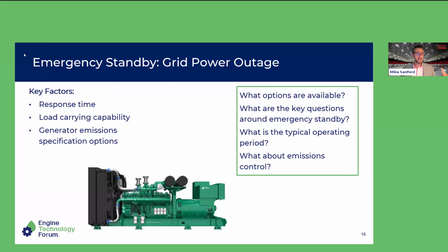That transfer could result from a total failure of the normal power source, an outage, or simply a brownout condition where voltage or frequency have decayed to a point where they're technically still present but not serving the loads appropriately. In that case, the transfer begins to take place.